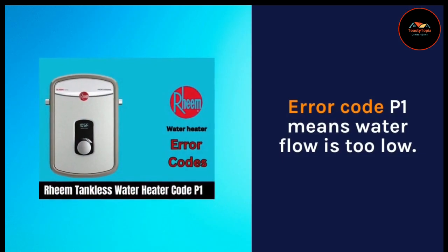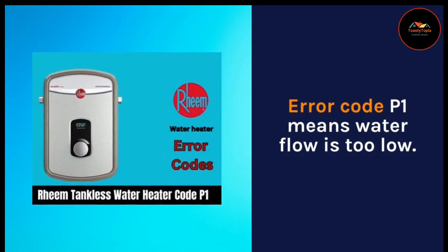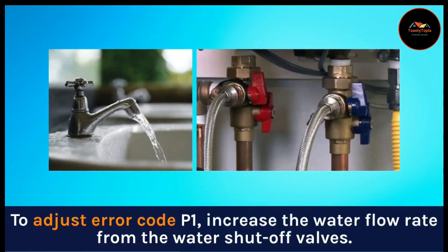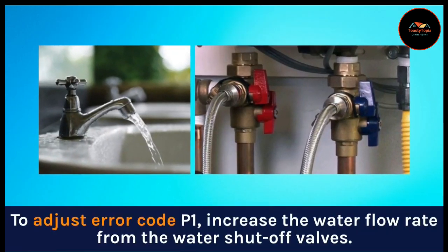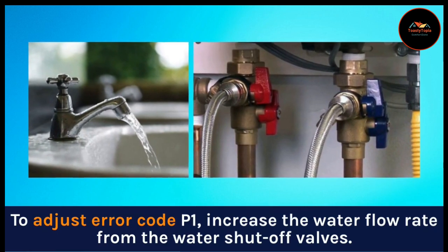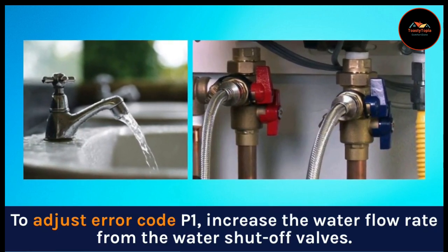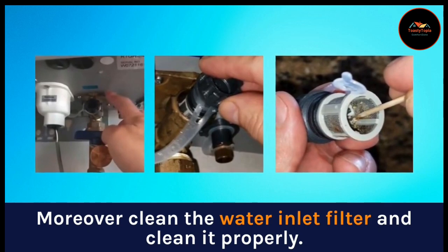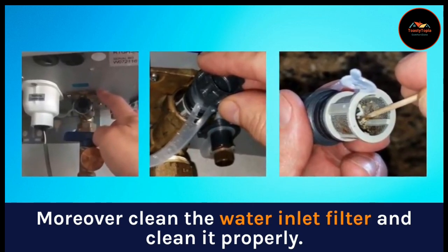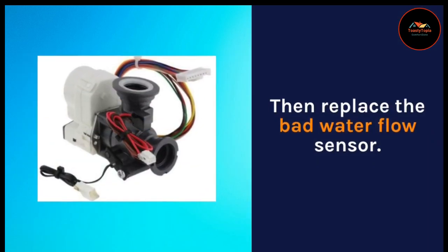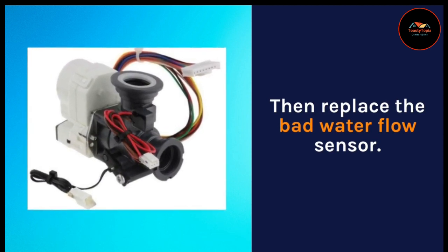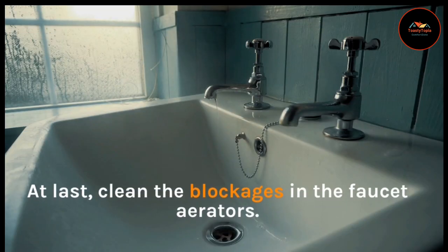Error code P1 means water flow is too low. To fix error code P1, increase the water flow rate from the water shutoff valves. Clean the water inlet filter properly. Then replace the bad water flow sensor, and clean any blockages in the faucet aerators.